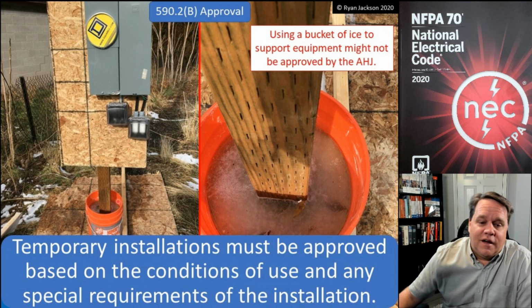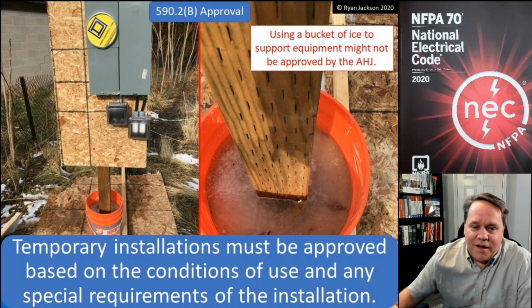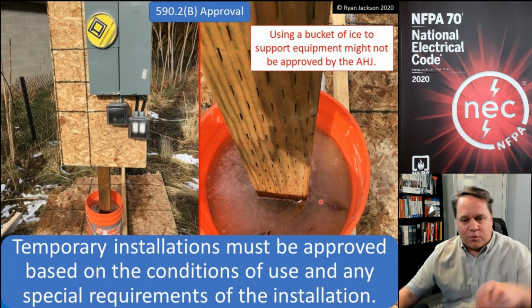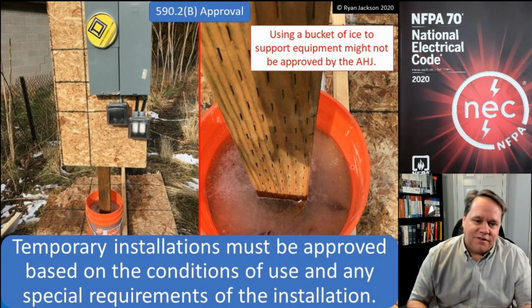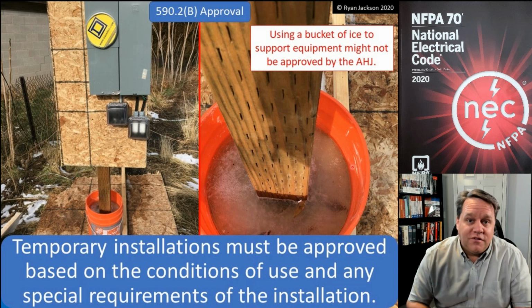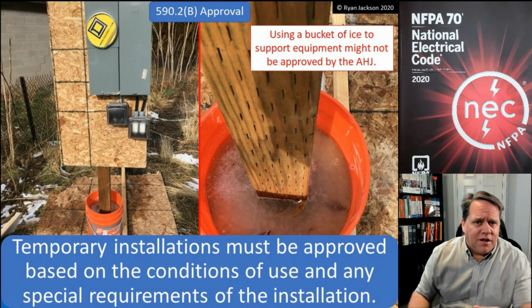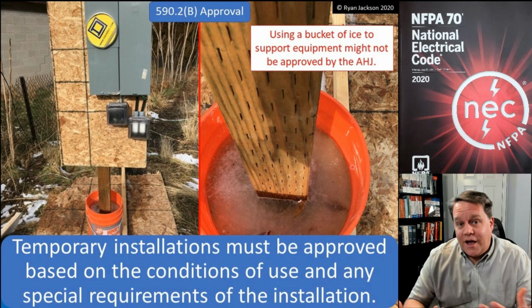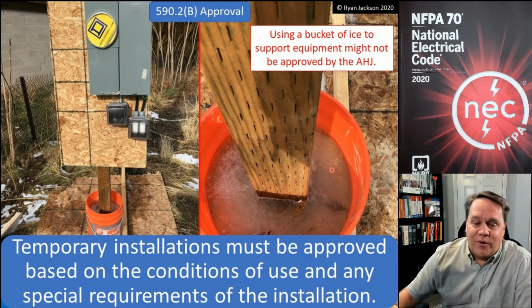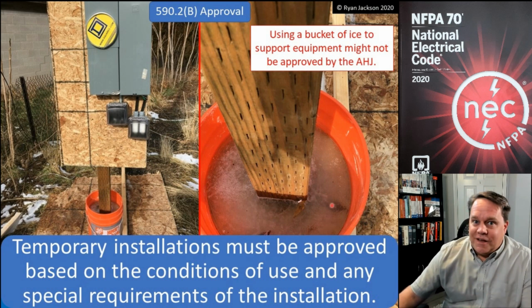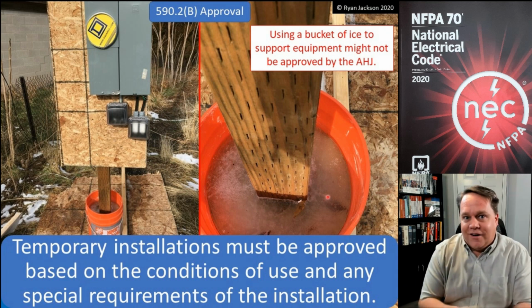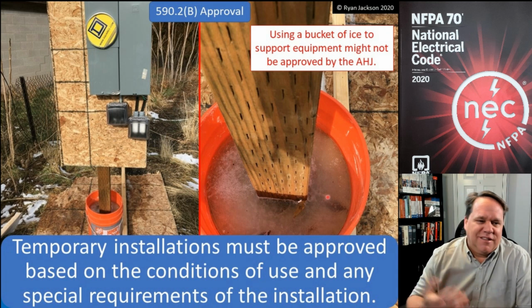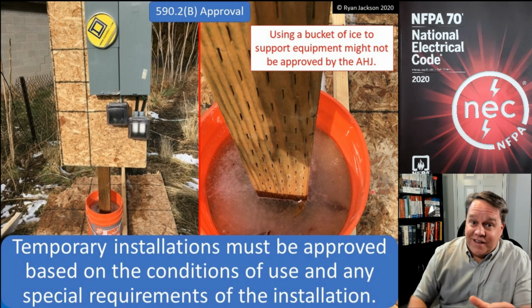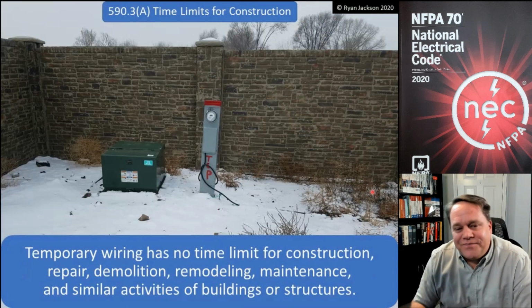They actually, this is in the middle of winter, they were supporting their temporary pedestal with a bucket of ice. So, just pour some water in there, and it's Salt Lake in January, it's going to freeze. This kind of puts a time limit on it. You better be done with the project by April or your temporary power is going away. But stuff like that, obviously the NEC doesn't exactly address. It leaves it up to the AHJ, and for good reason. So suffice it to say, she didn't pass this inspection.